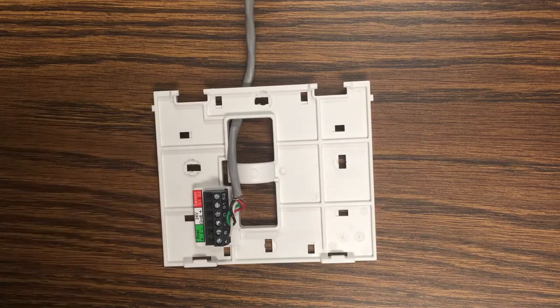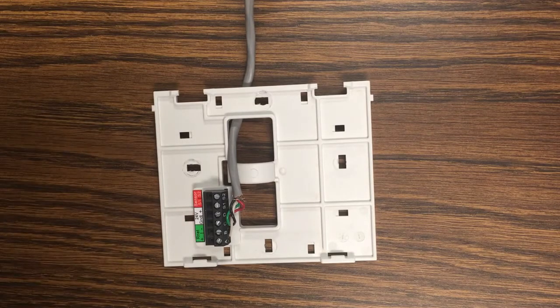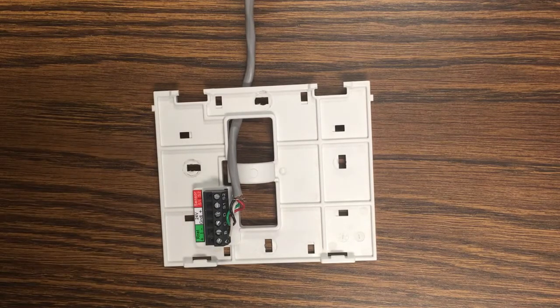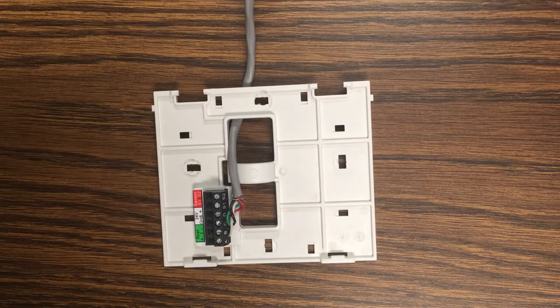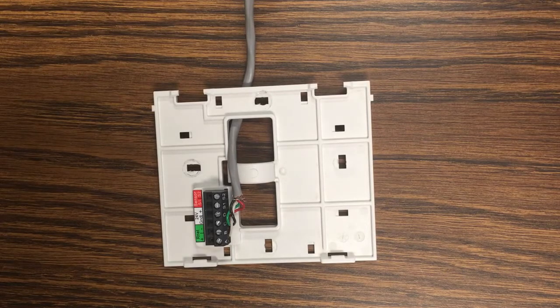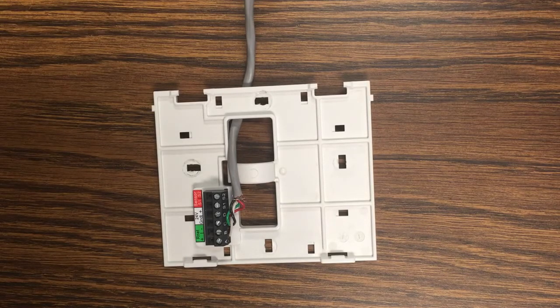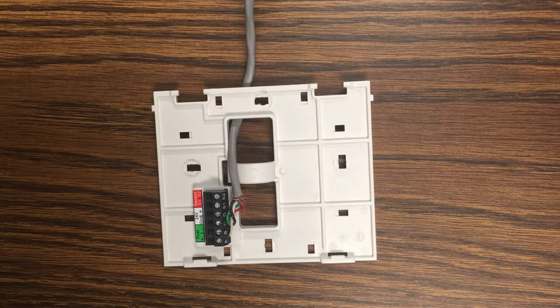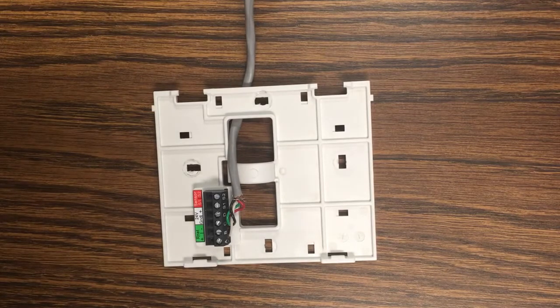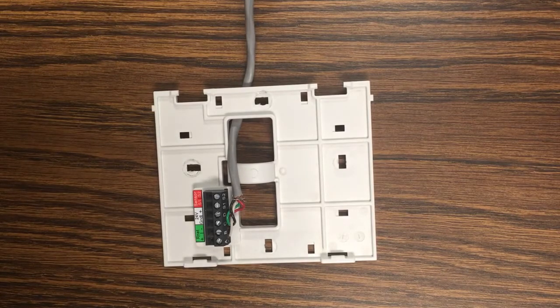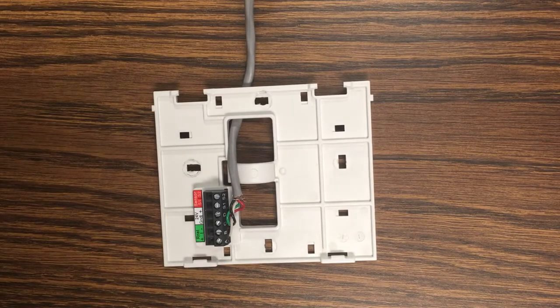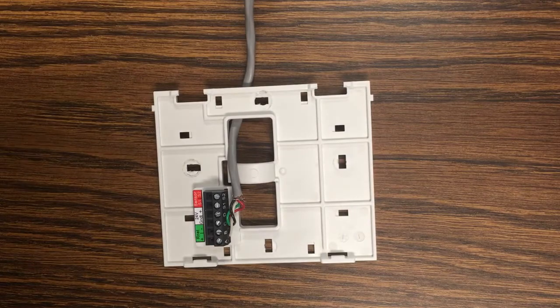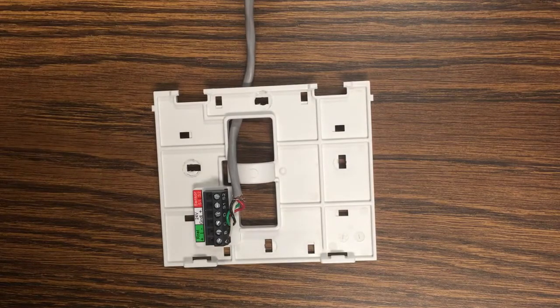The touchscreen has its own built-in temperature and humidity sensor but if you wanted to run another sensor maybe to a different space you could wire it in here and with a couple changes in settings on the touchscreen it would use that as its room temperature instead. We'll talk about that in a little bit.